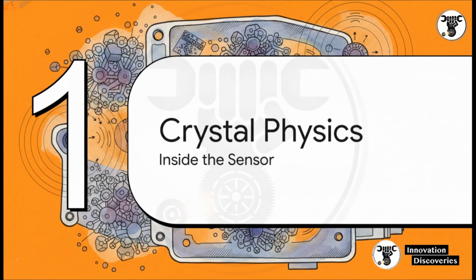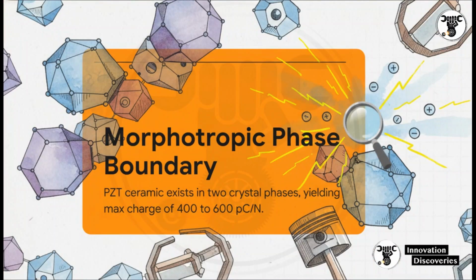All right, Section 1, the piezoelectric crystal physics. To truly grasp how this thing does its job, we've got to zoom way in, right down to the microscopic level inside the PZT ceramic disc at the heart of the sensor. Now, the magic really happens at what we call the Morphotropic Phase Boundary, or MPB. We specifically engineer the PZT, that's Lead Zirconate Titanate, ceramic to sit exactly on this boundary. Why? Well, because existing in two crystal phases at the exact same time is the absolute sweet spot.